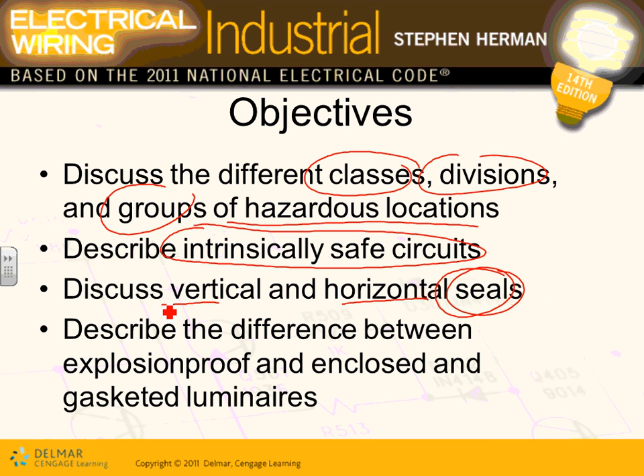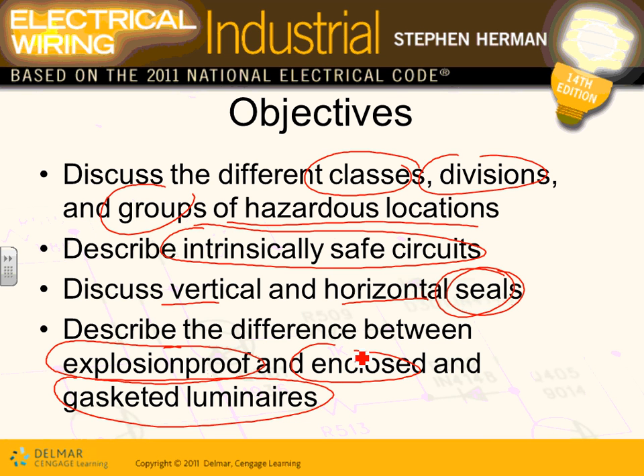A good example of a hazardous location is a gas station. A gas station has flammable gases, vapors and liquids. So do you think you're going to put a circuit breaker right in an area where it's flammable, and every time you turn that circuit breaker or switch on and off, you create a big explosion in the gas station? So these areas use special equipment and special wiring methods, and then they have to have a seal. We'll talk about seals in a second. The equipment they use is explosion-proof equipment, as well as enclosed and gasketed luminaires.